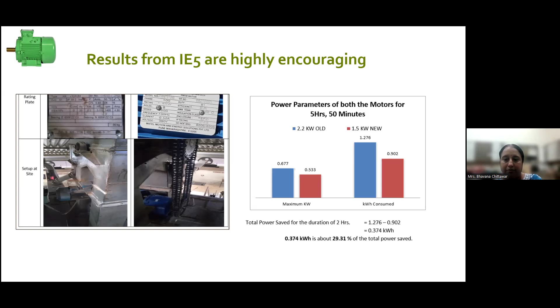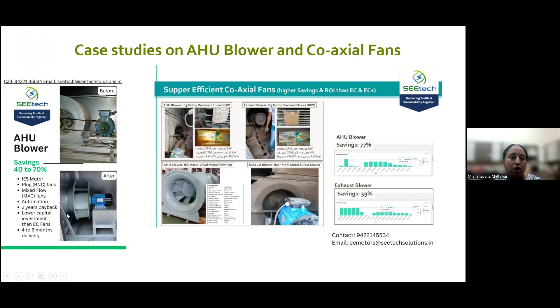Now the next technology is for AHU blower and coaxial fans. In case of AHU blower, since these are efficient blowers, plug fans and mixed flow fans are used, with some automation required for VFD. Here the payback period was 2 years, and the capital investment is also lower than EC fans. We compared it with EC fans, and the payback period is less than 2 years.